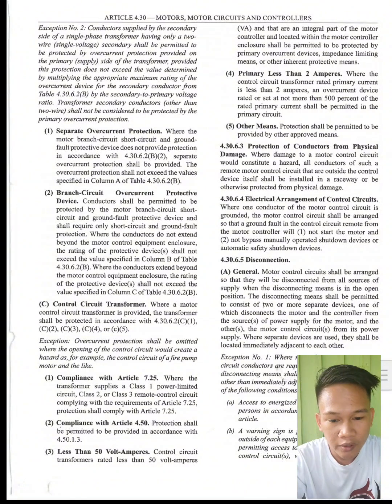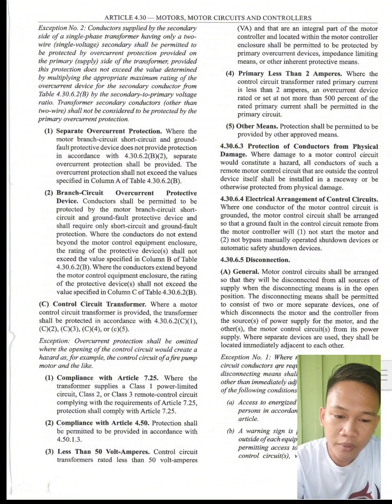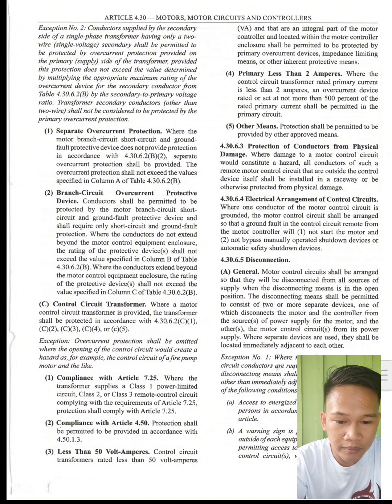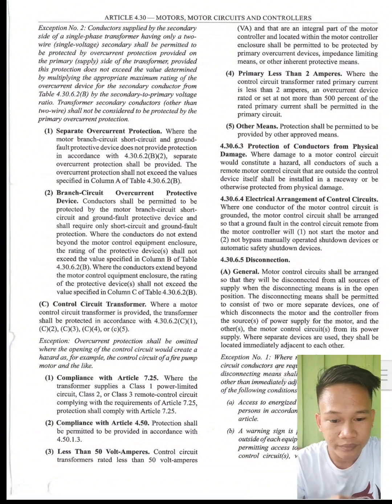Next, we have control circuit transformer. Where a motor control circuit transformer is provided, the transformer shall be protected in accordance with 4.30.6.2 C1, then C2, then C3, C4, or C5. Exemption: overcurrent protection shall be omitted where the opening of the control circuit would create a hazard, as for example, the control circuit of a fire pump motor and the like.